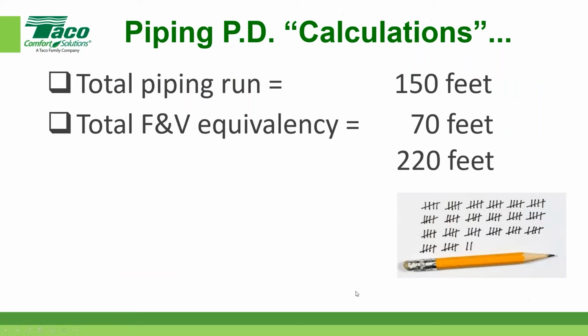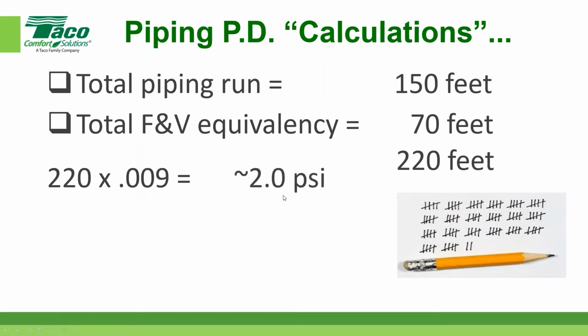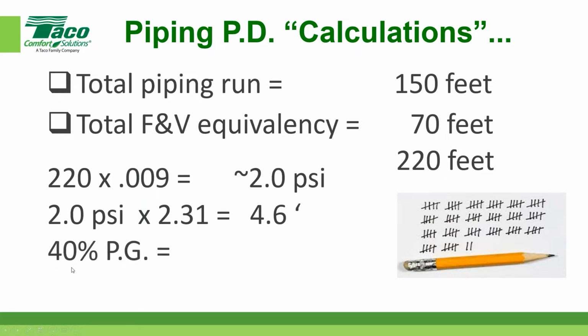So, all right, let's do that math together. I'm using the copper number. Okay, 220 times 0.009 gives me 2 psi. We always got to convert psi to feet of head with this number right here, 2.31. So 2 psi times 2.31, we can assume we'll have about 4.6 feet of head on that particular run if it was just water. What if I had propylene glycol at 140 degrees? Well, there again, that's about 25% additional pressure drop, and so you have to account for that. So you're going to be closer to 6 foot of head with a glycol. Just remember, the viscosity of the fluid affects the circulator's ability to pump. So that's why you got to make sure.